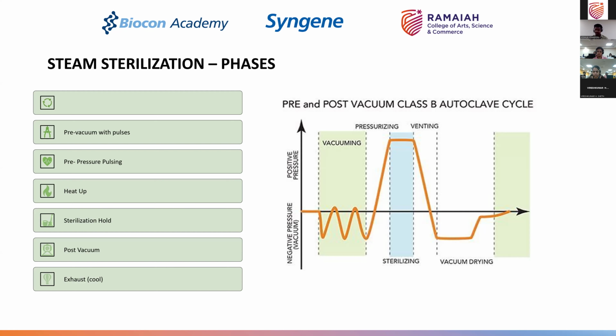Then you introduce steam, which also displaces the air from the chamber, and therefore your chances of any air being inside the system are almost reduced to zero, and therefore you do what is called a pre-vacuuming phase. So that is this preconditioning phase.